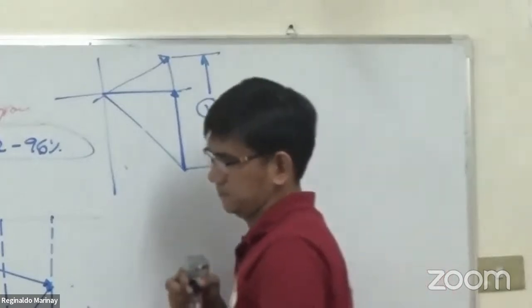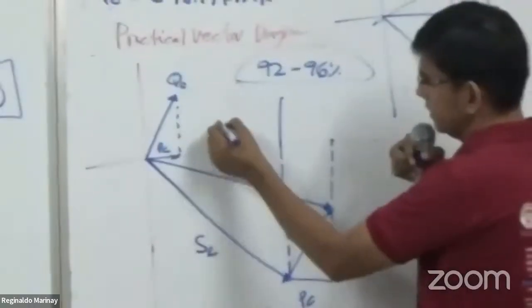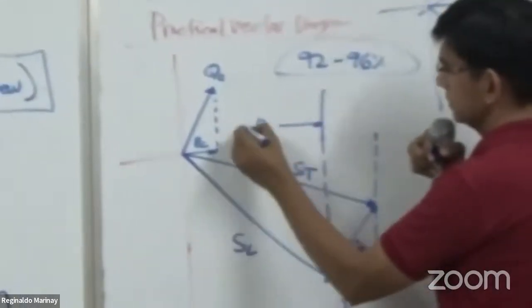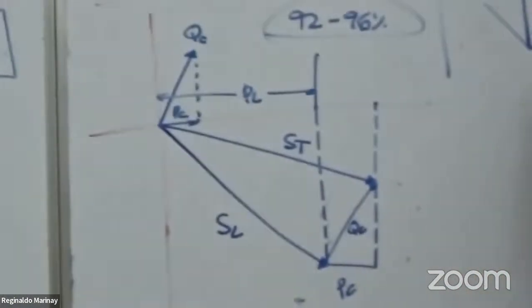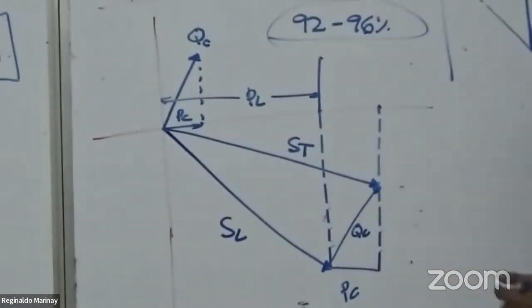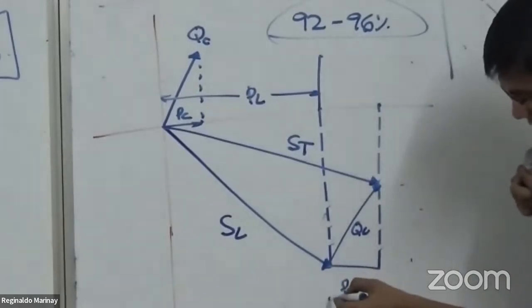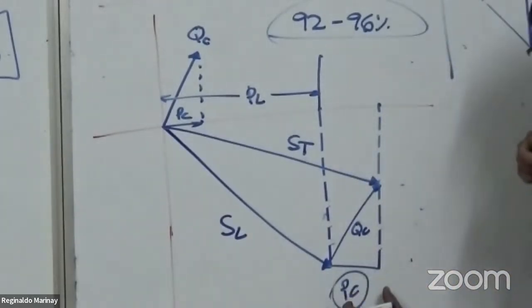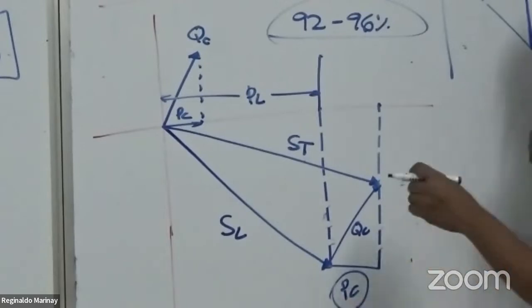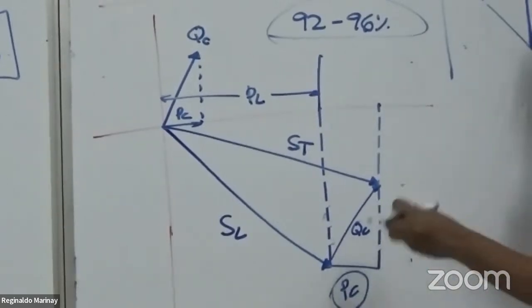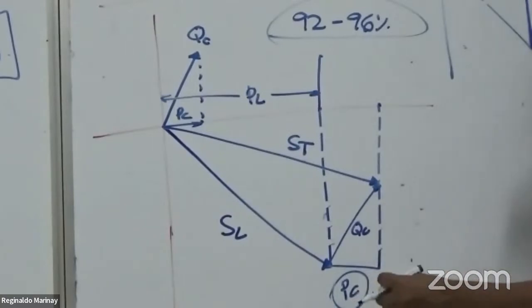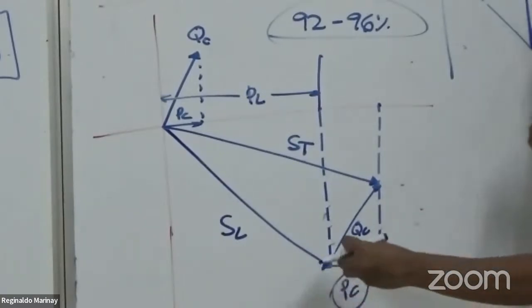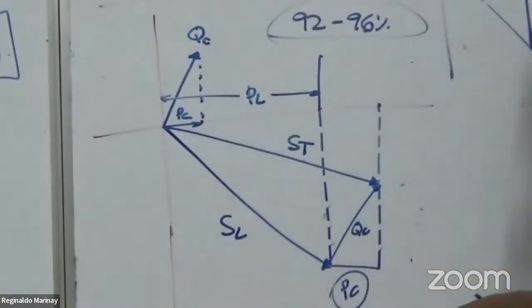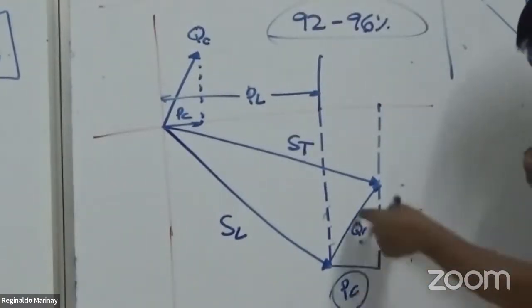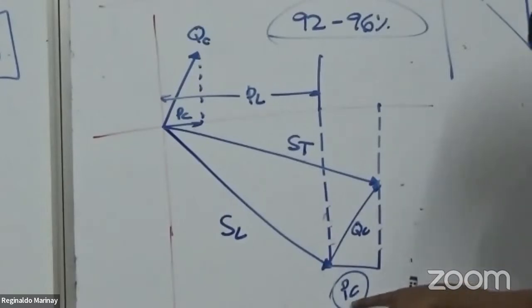What do I mean here? We have the SL, we have the PL. Now, the PC here is an additional load for the supply. Your capacitor itself has a real power, it has watts. That is an additional load taken from the supply, the power you need to energize your capacitor.